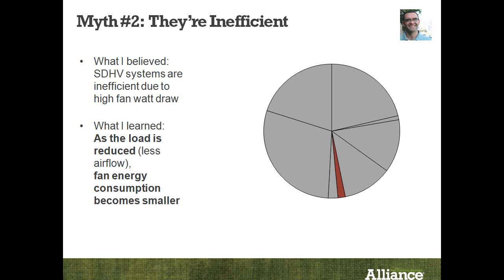Let's go to the example of 800 CFM. If you had 800 CFM, you're going to be using a lot of watts to move that air. A new low-load home is closer to 600 to 400 CFM. So compared to an old system, you can almost have twice as much fan watt draw, fan energy consumption, and you still aren't going to be inefficient compared to the older system. It's a large part of the energy consumption, but the load on the home has gone down. So they aren't truly the most efficient, but they aren't inefficient the way people consider them to be.